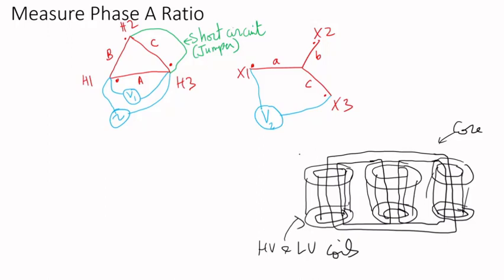if I call this phase A, phase B is in the middle, and phase C is the other leg. When you energize the high voltage, for instance, flux will be induced in each core leg, and that flux will link or try to link the other winding to induce voltage in it. Now the way we represent that, to show which phase A high voltage, which low voltage, schematically, this is what I'm showing as phase A. I'm going to highlight phase A here. Then I'm going to find in the Y side the phasor that's parallel. Because it's parallel, those are in phase because they're wound around the same core leg, and the same flux will link them.